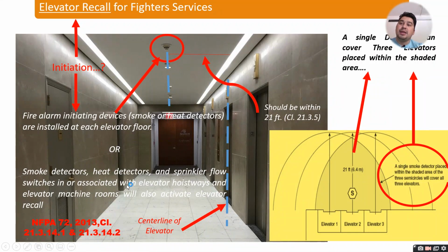It is required as per NFPA 72 2013, clause number 21.3.14.1 and clause number 21.3.14.2, and should be within 21 feet, clause number 21.3.5. It should not be more than 21 feet.